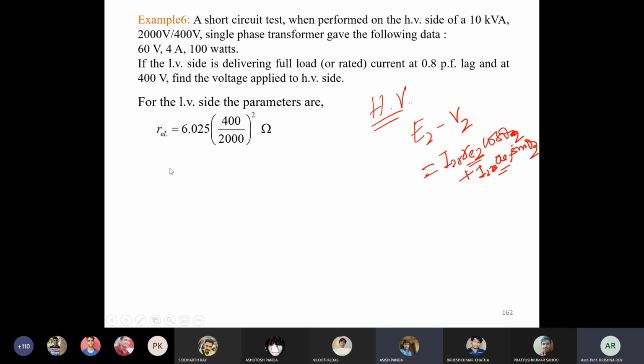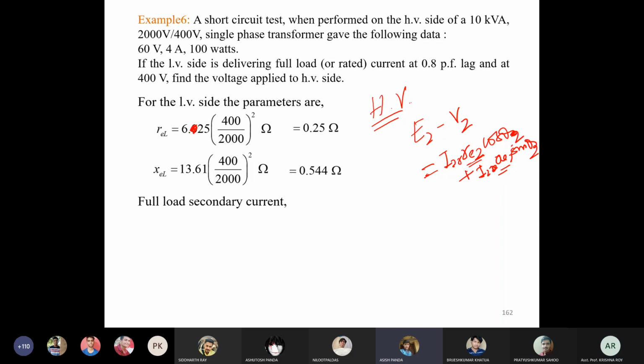Okay, so 6.25 will be multiplied into the turns ratio square. Calculate this, and also XEL. Now calculate the full load secondary current, that is 10,000 divided by 400, which is 25 ampere. So that is the secondary rated current.